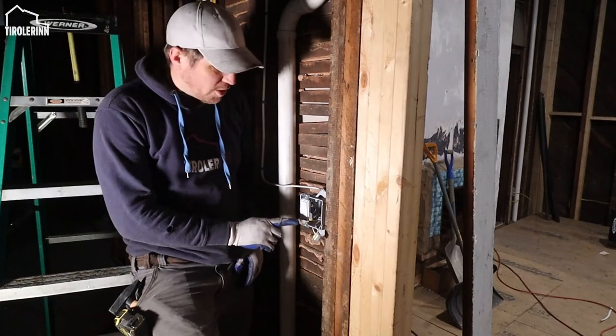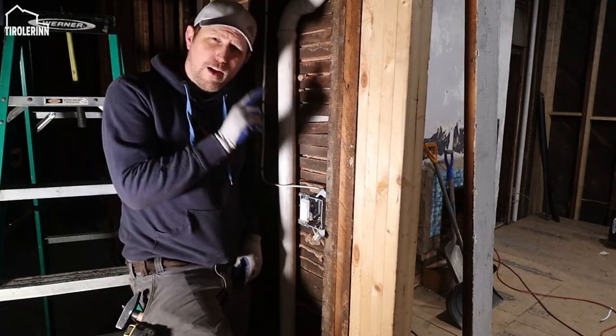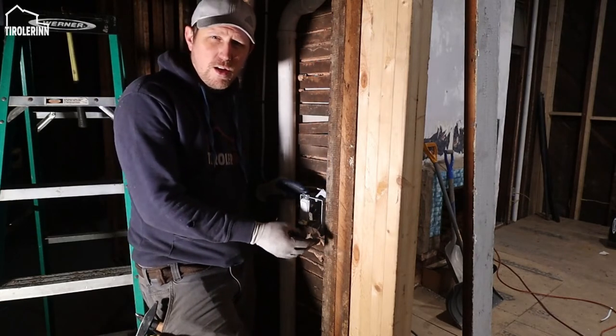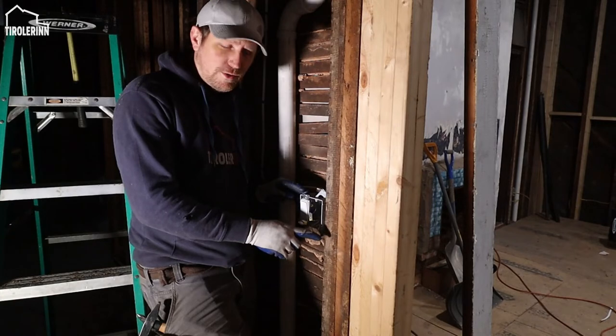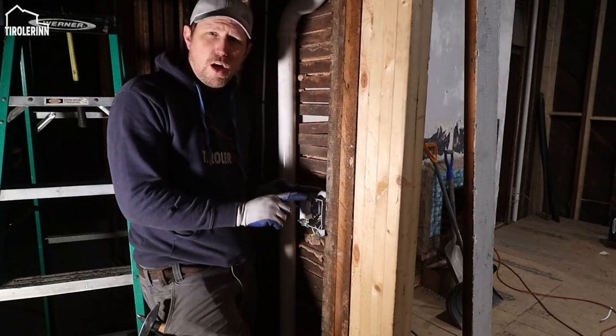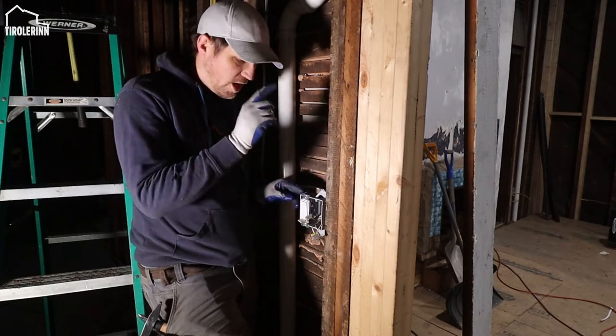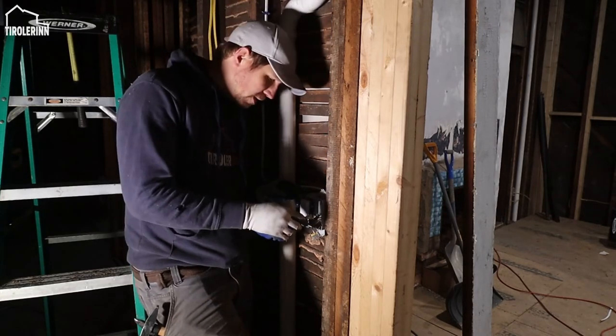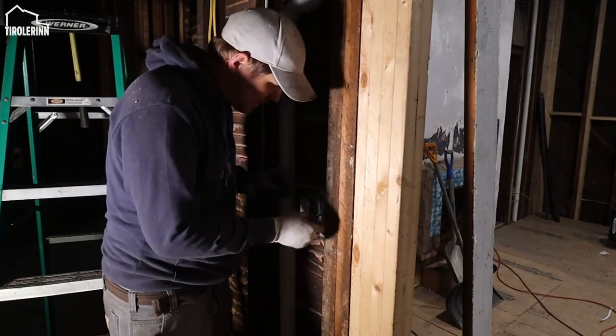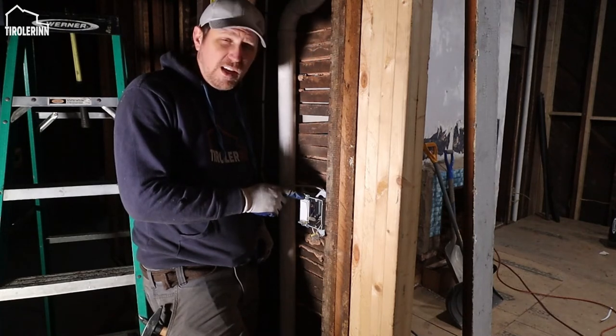If you're wondering why I'm using these connector pieces everywhere, everywhere where I have a double light switch, I only want to have one power coming in. And with that one power coming in, I need to split it into three neutral out and three hot out. And then also I need to split the ground into four. The reason why I need four is because each line always gets a hot or a neutral in, but then also the light switch itself will get a piece of ground.